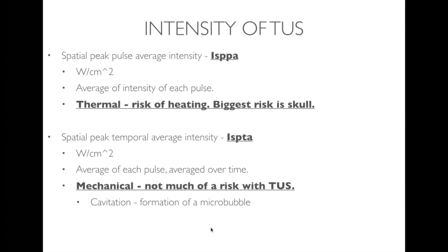The thing with cavitation is that NeuroFUS has been designed to avoid the risk of cavitation altogether, and it can't actually operate at a power high enough to produce it. So the NeuroFUS system is limited to an intensity of 30 watts per centimeter squared ISPPA by standard, and you can unlock it to operate at 60 watts per centimeter squared if you like, but it still can't reach a power high enough to cause things like cavitation.